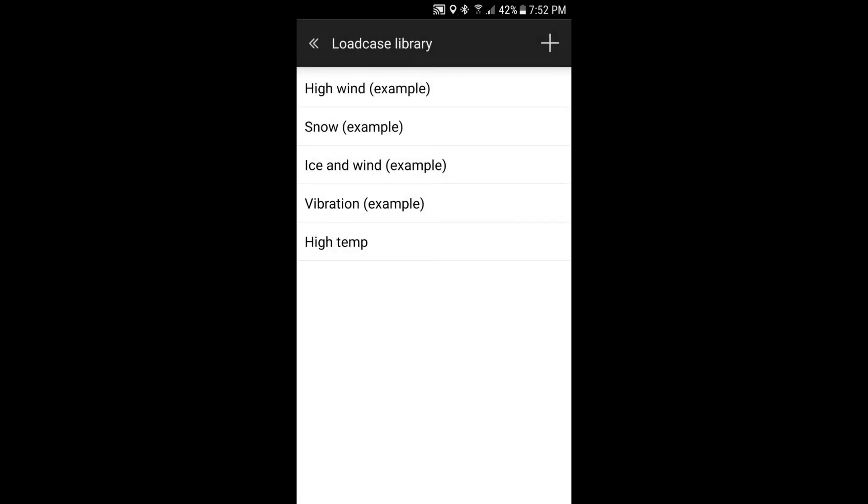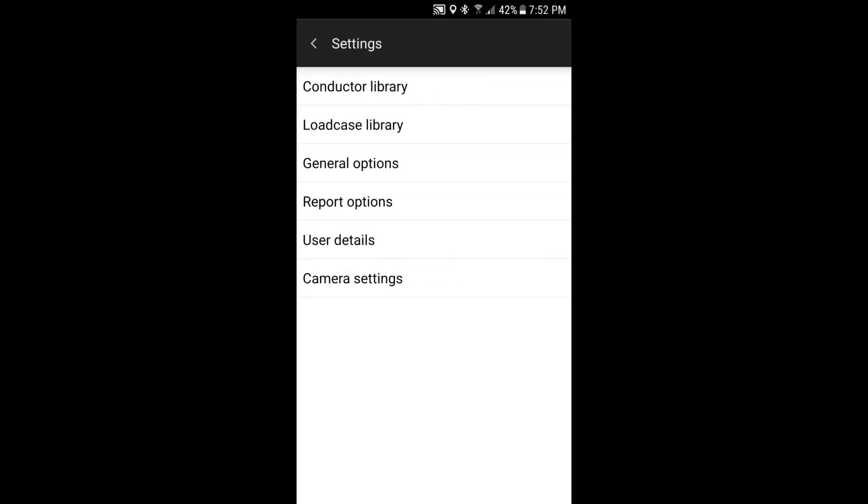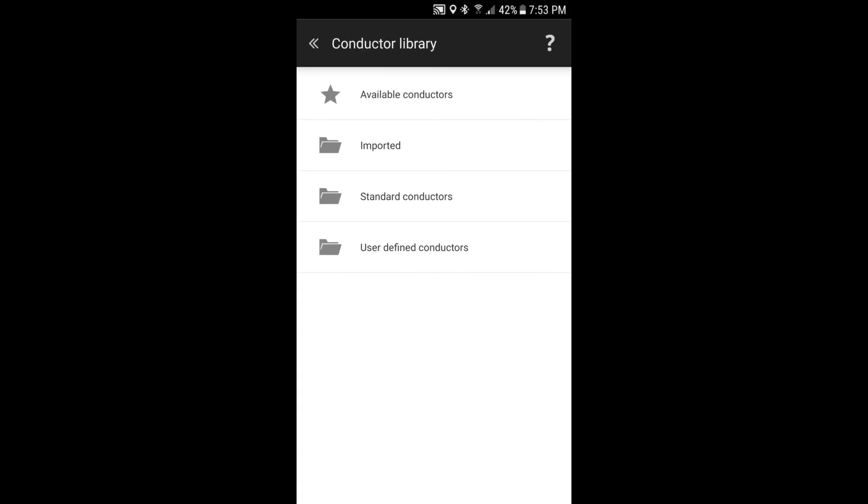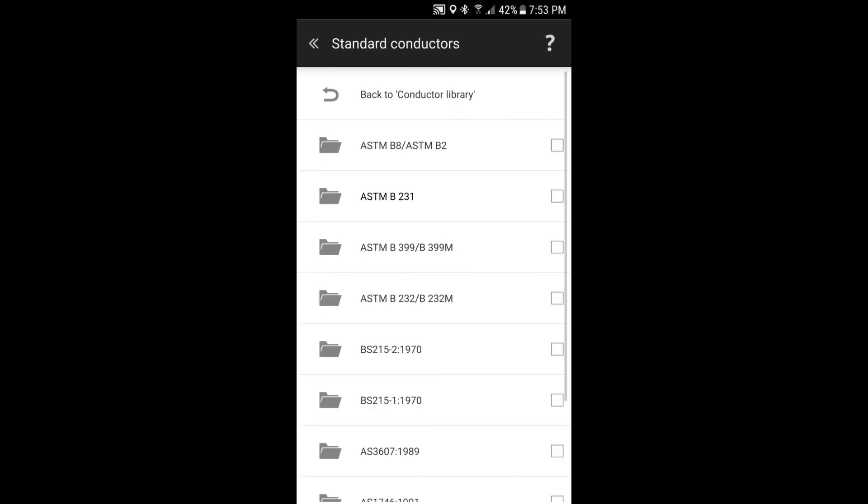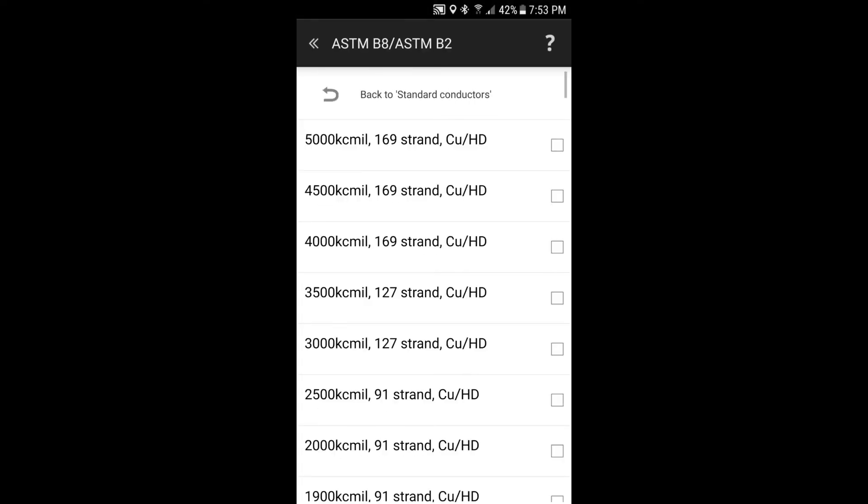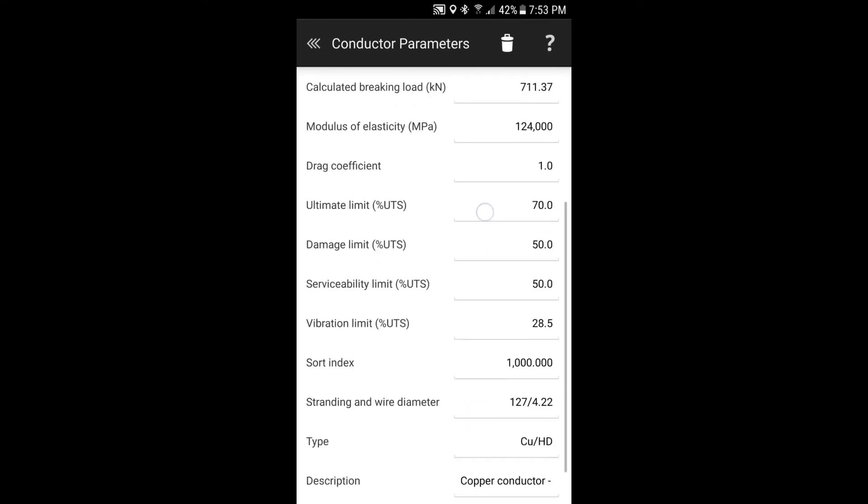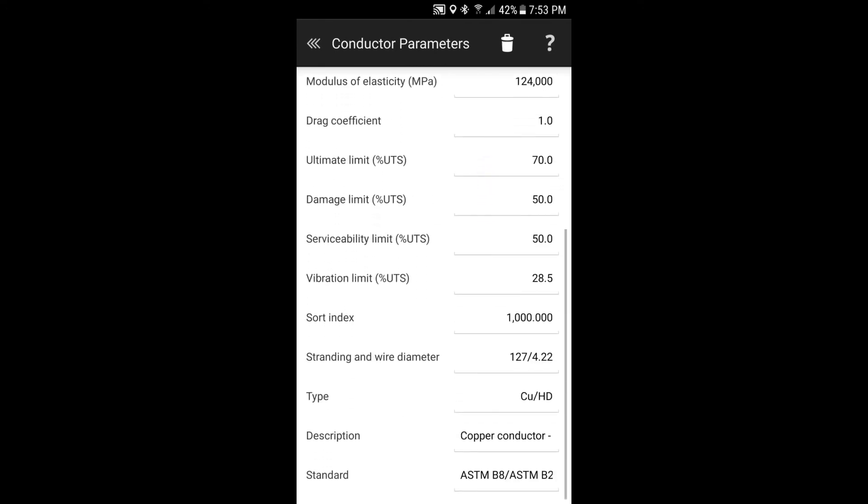And how this is used is if we look, if we go back and we look in the conductor library. And if we just select one of the conductors and just take the first on the list. And you see down here, we've got ultimate limit, percent UTS, damage limit, percent UTS, serviceability limit and vibration limit. The percentage of your ultimate tensile strength of your conductor. These are your conductor material strength factors that relate to the load case that you're putting in. Sometimes you might have a load case that's specific to a certain limit state. And so this allows you to reflect that.